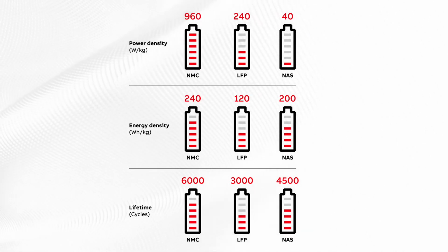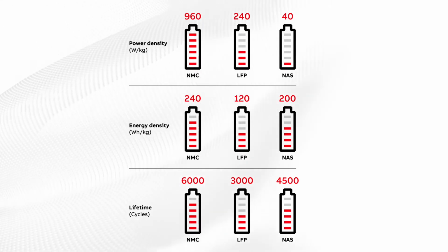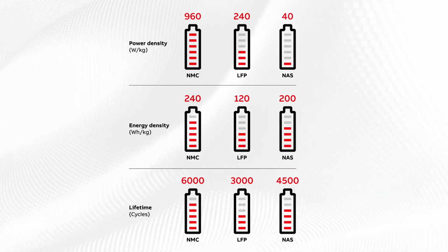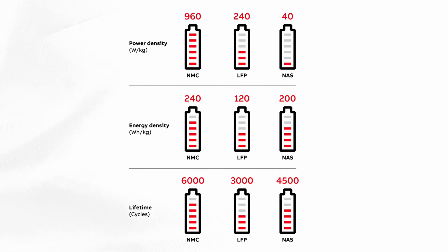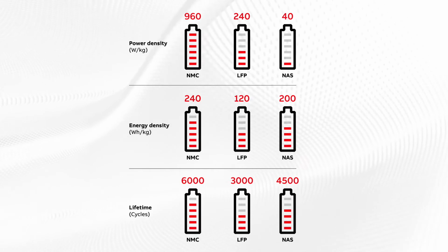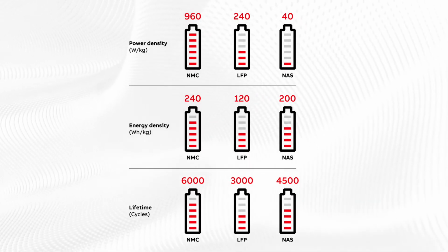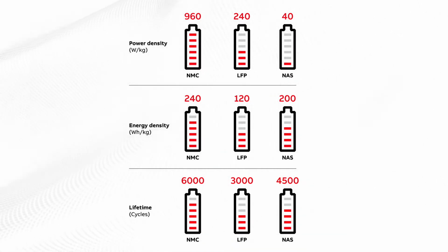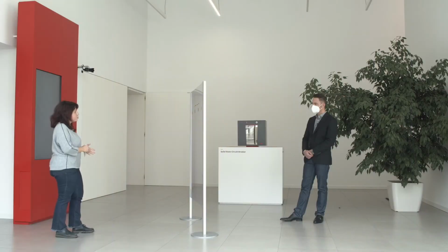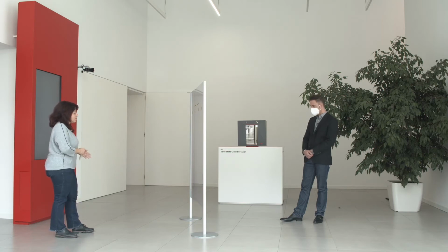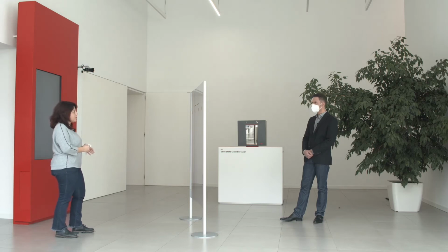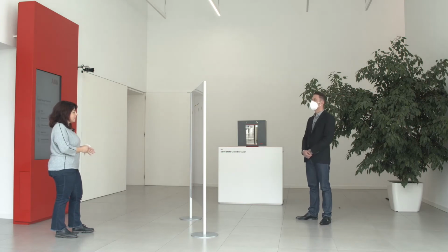This battery belongs to the family of the high-temperature batteries, so-called because their internal operating temperature is very high. It is around 300 centigrade degrees, necessary to keep the electrodes in a molten state. This technology is very different from the lithium-ion battery, which is very modular, because the sodium-sulfur battery is produced by only one manufacturer in the world, and it is possible to buy only a containerized battery system with a very big size, starting from 1.2 megawatt-hour on, and already equipped with auxiliaries, protections, battery management system, and power electronics.